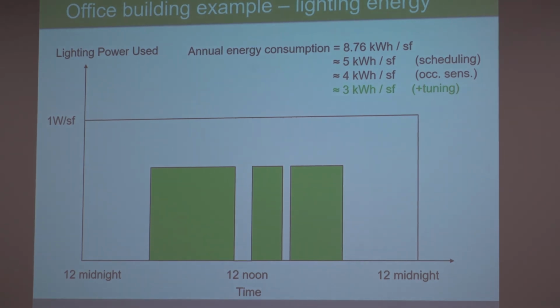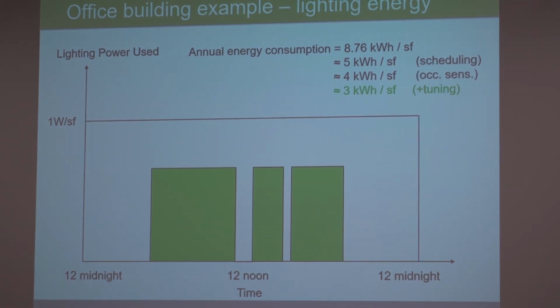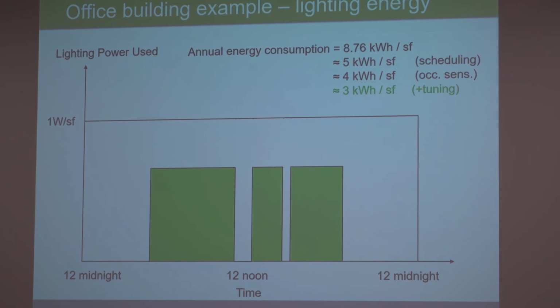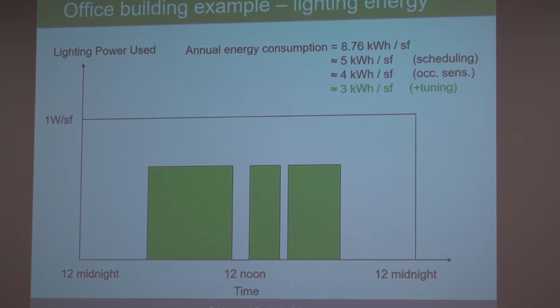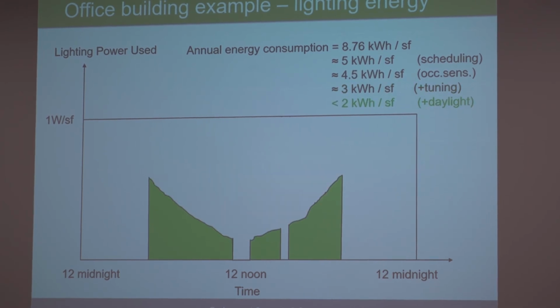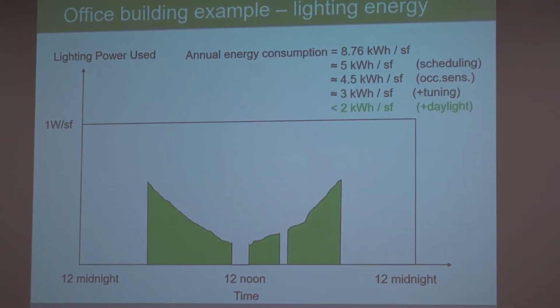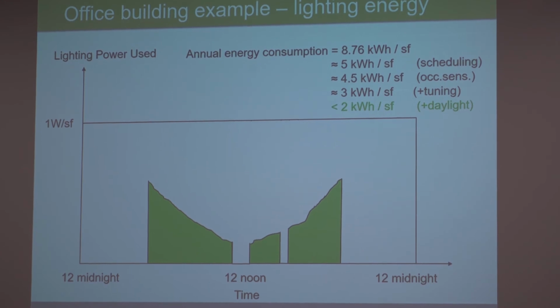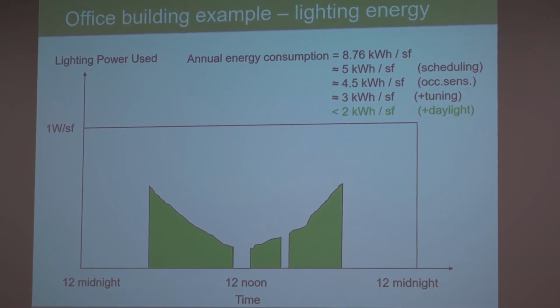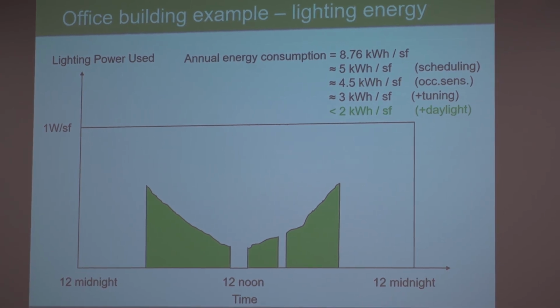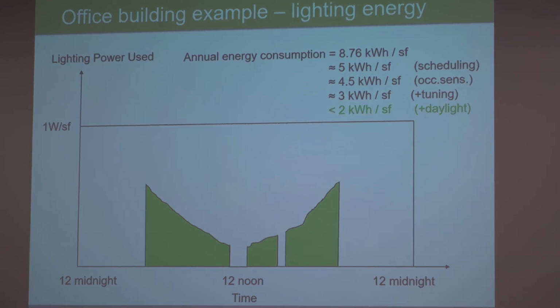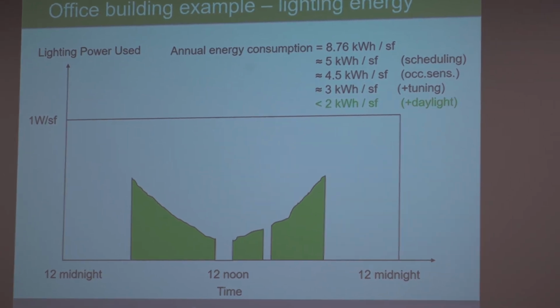You do the high-end trim or light level tuning, setting the maximum light level lower than the true full-on level. Now you're down to about 3 kWh per square foot per year. You do daylight harvesting, taking advantage of the daylight that's coming into the windows and skylights to illuminate the space. Now you're down to less than 2 kilowatt hours a square foot each year of lighting power. Okay, so you can see that these strategies build on each other, and the more strategies you do in the commercial buildings, the more energy you save.